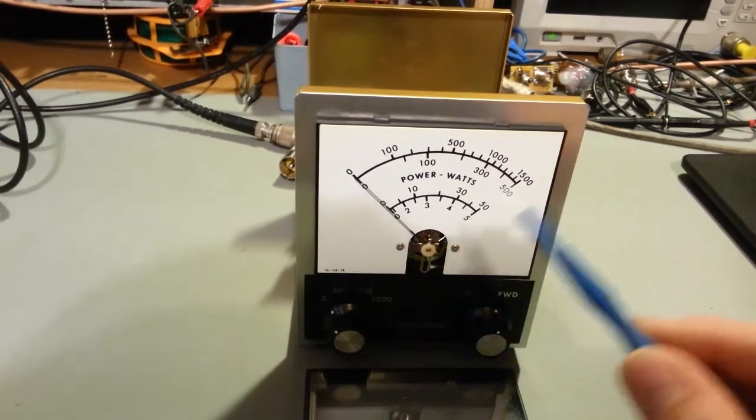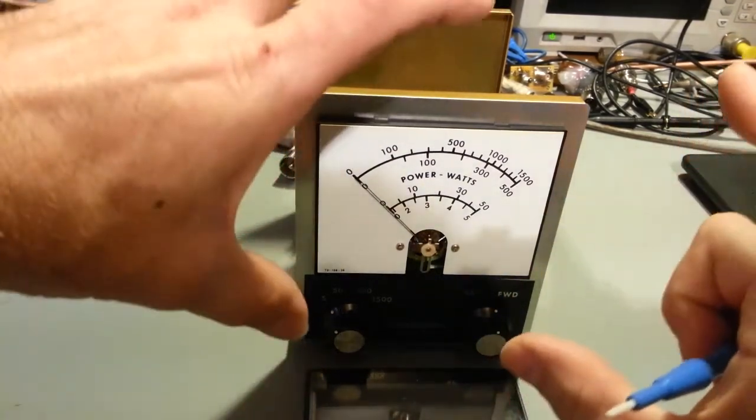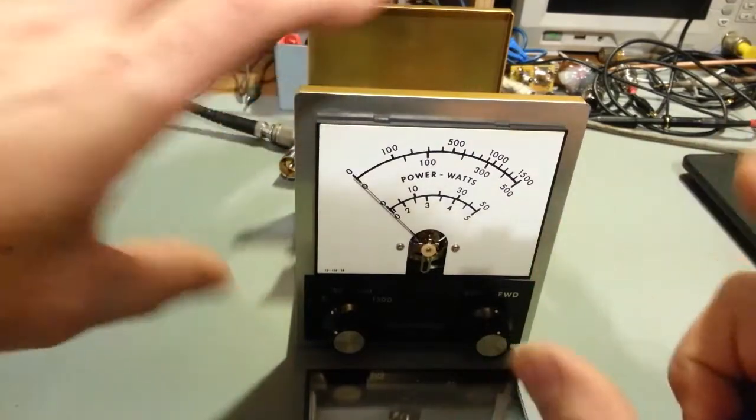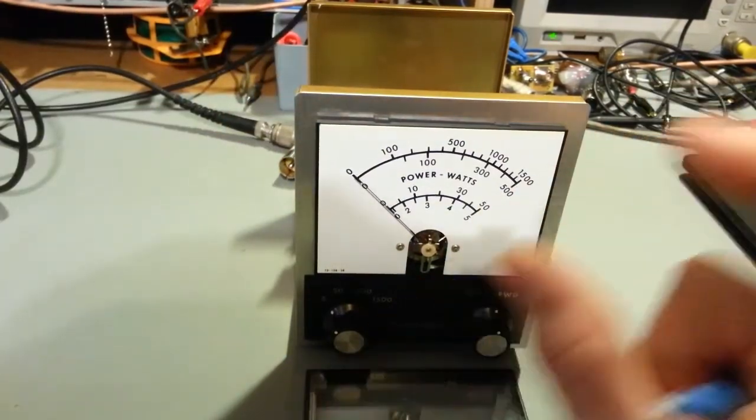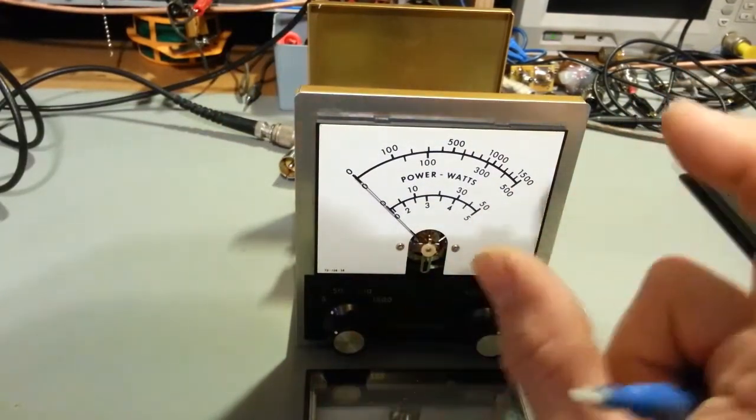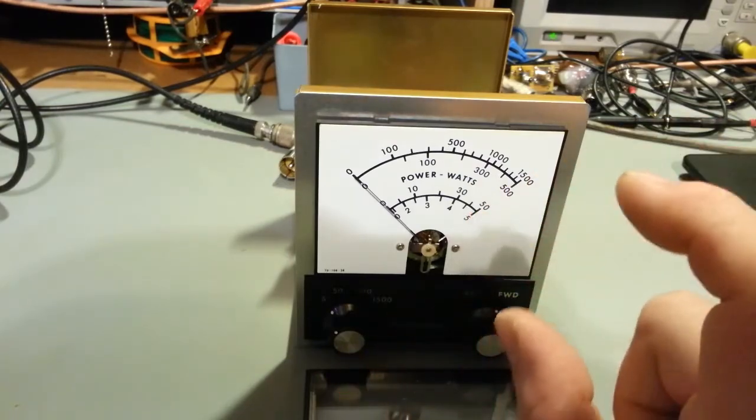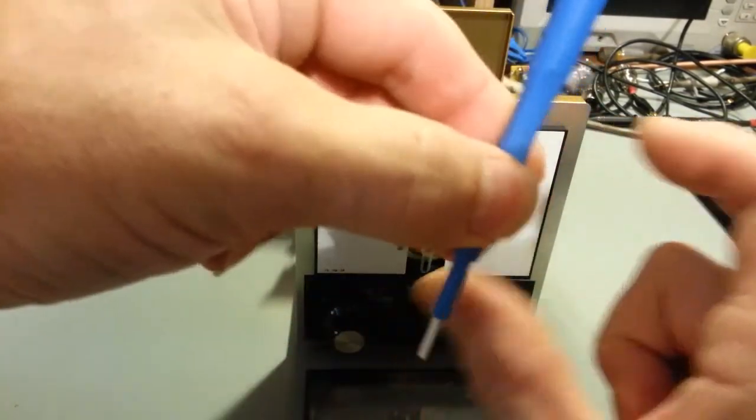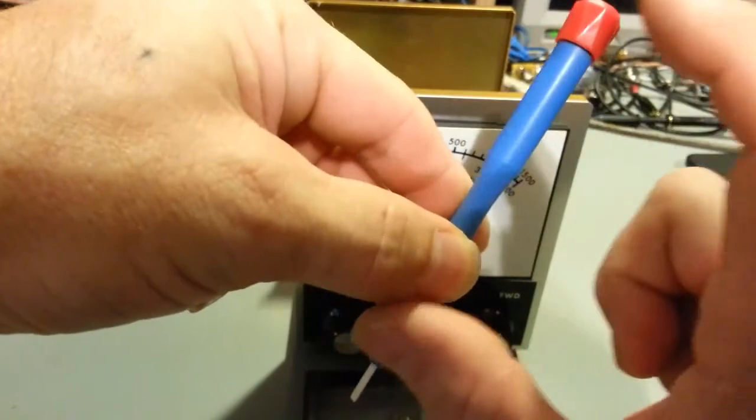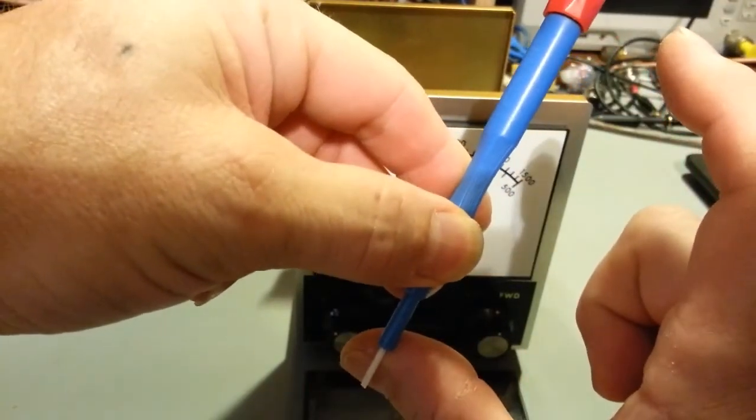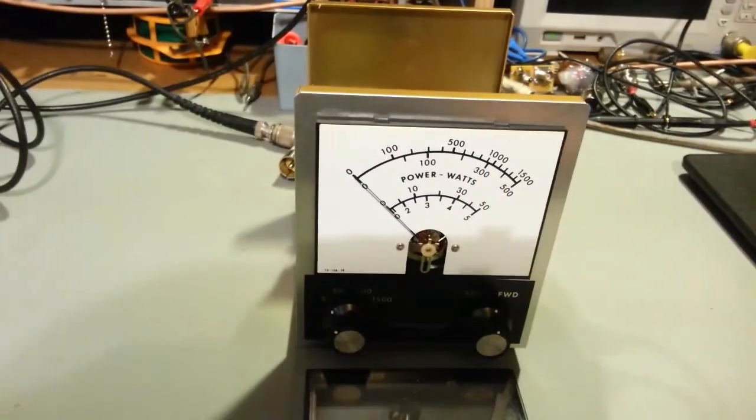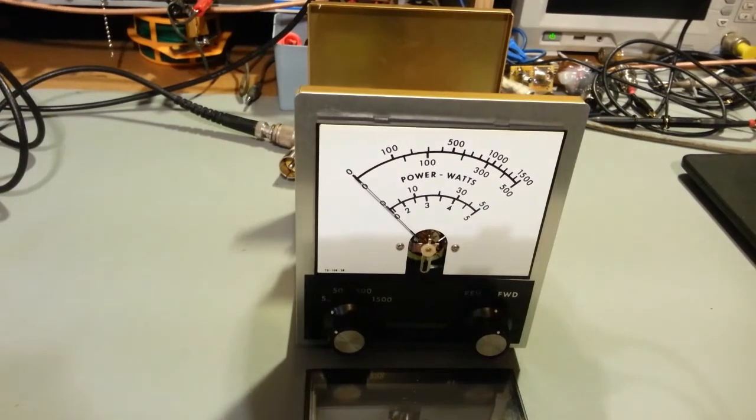Just make sure your spring didn't get, anything I can figure is, it took a hard hit in this direction, like that. The spring, the whole spring assembly kind of wobbled like this and got down underneath, and then that outer coil, basically when that spring assembly got down underneath the outer wrap of it, got underneath that little piece of metal that sticks out there. So, there you go. Just a quickie video on things to look for if you have a funky operating meter movement.